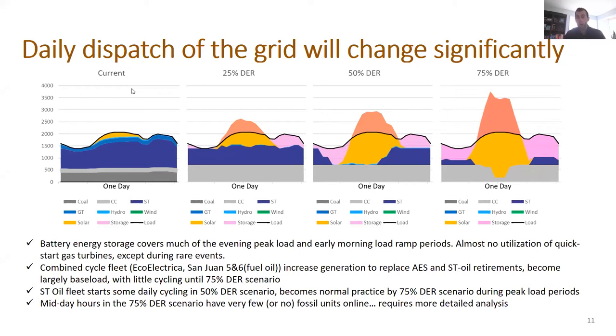And so this is one representative day. Again, we replicated this across the entire year, but you can see the average daily generation profile. In the current case, very minimal solar is shaving off some of the peak load in the middle of the day. And then as we increase the DER, it's pushing down the fossil in the middle of the day with some of the solar going onto the grid. The remainder, the area over that load curve, that's what's going into the batteries, charging into the batteries, and then later discharging in the evening and overnight periods.